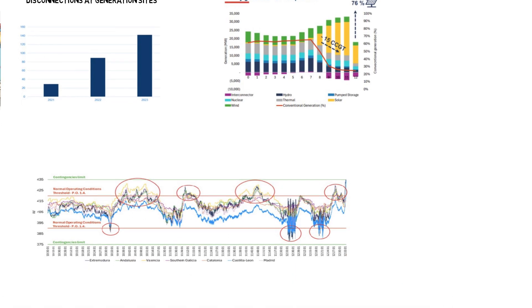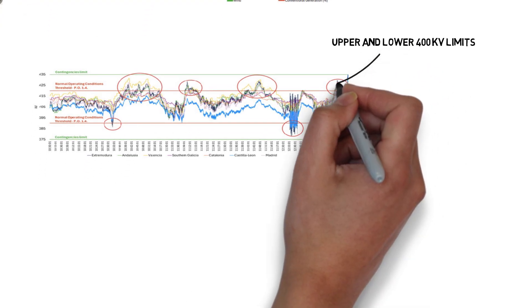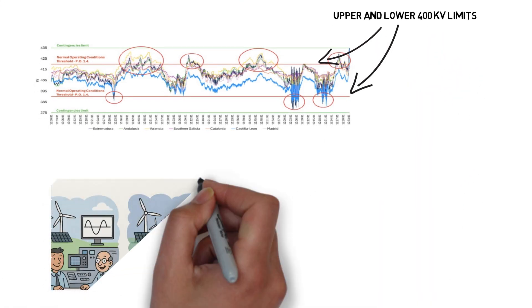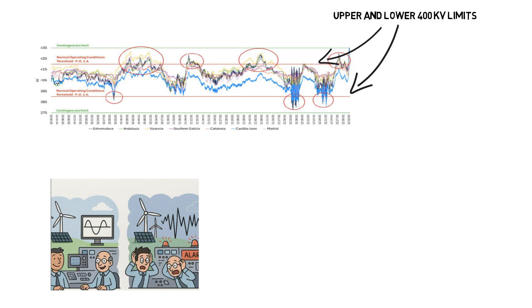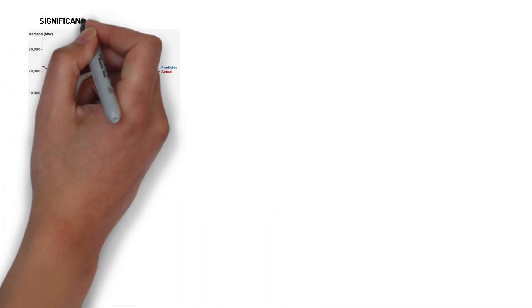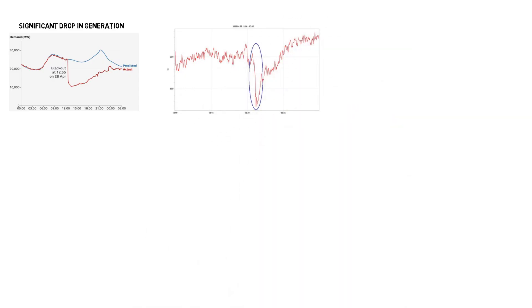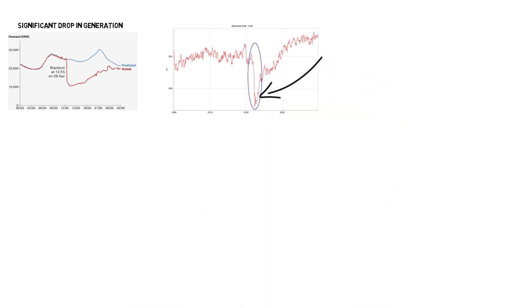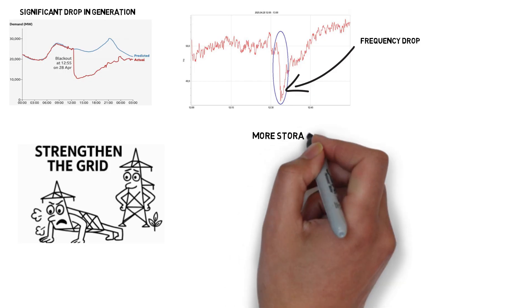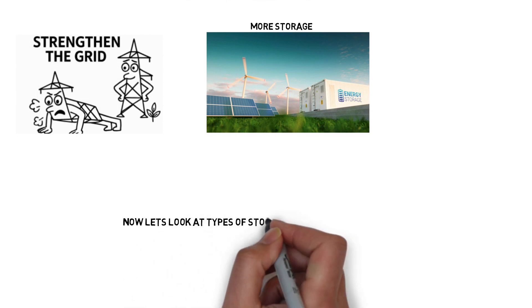This reduced system inertia and reactive power control. As conventional generation continued to drop from the grid around 10:30, the system began experiencing voltage deviations beyond acceptable thresholds, marked repeatedly by red line indicators, before ultimately descending into instability. The delayed response to earlier warning signs led to cascading failures, resulting in over 2,000 megawatts of renewable generation being lost in seconds. Before this sudden loss of power, the system started to become unstable with large frequency oscillations. This event underscored the urgent need to reassess grid inertia, strengthen and review control systems, and invest in damping technologies like energy storage to prevent future incidents of this scale.